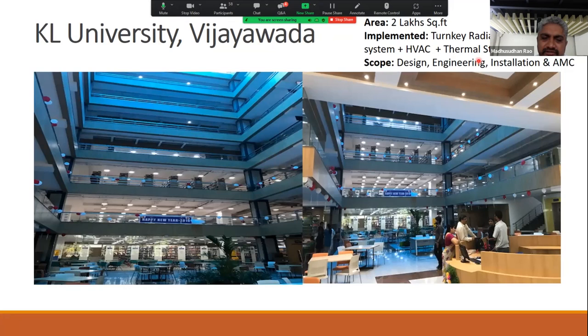This is a project in which this was done almost 10 years ago, and this is about 2 lakh square feet, but uses only 200 tons, because along with radiant cooling, thermal storage was used, and also heat recovery was used. So from the initial design of 16 air handling units, this was brought down to just 4 treated fresh air units with heat recovery. So this is one of the highly efficient buildings that we have executed.